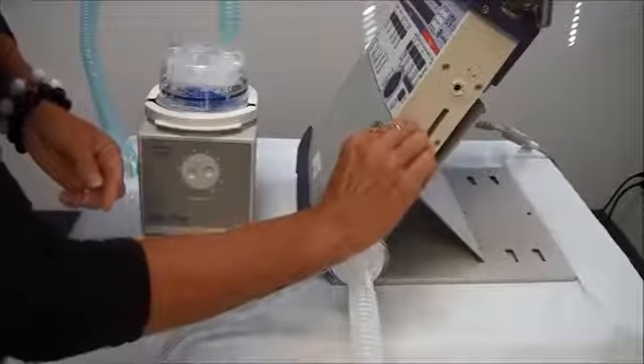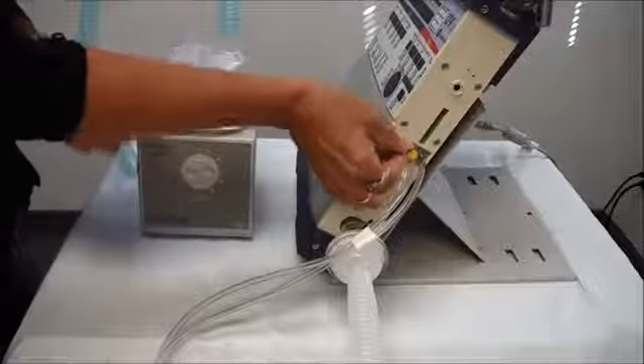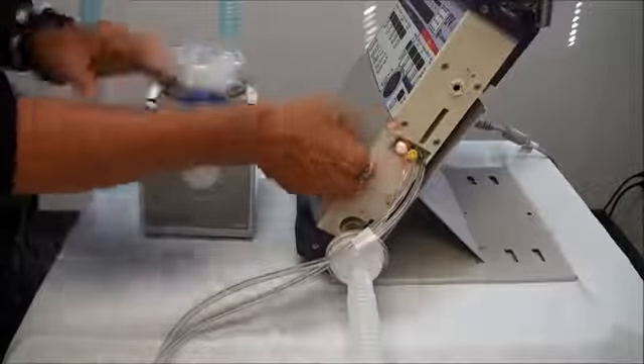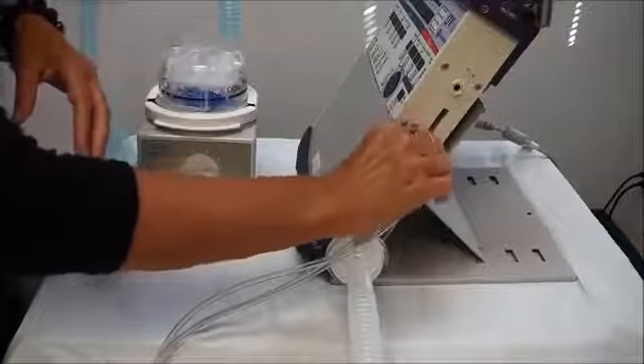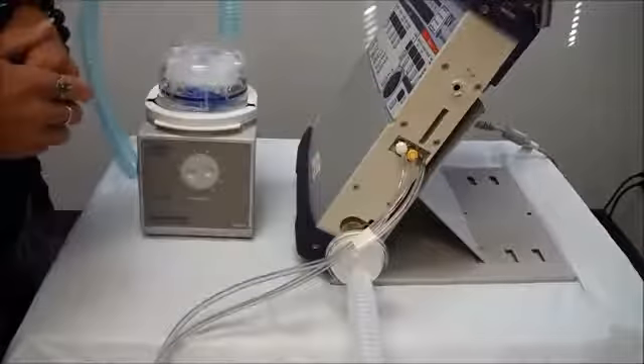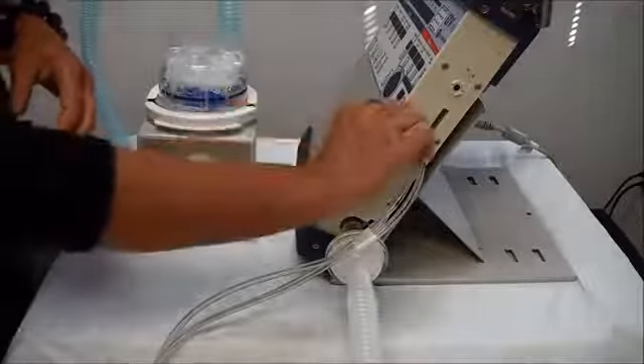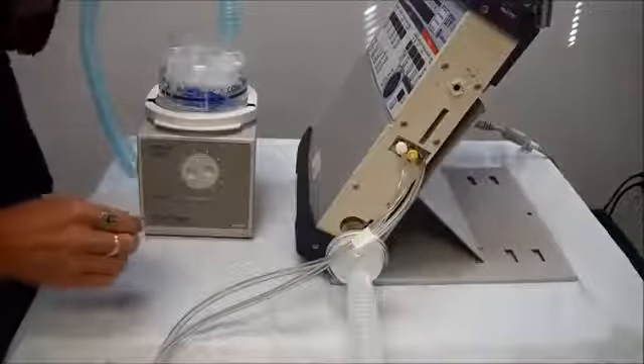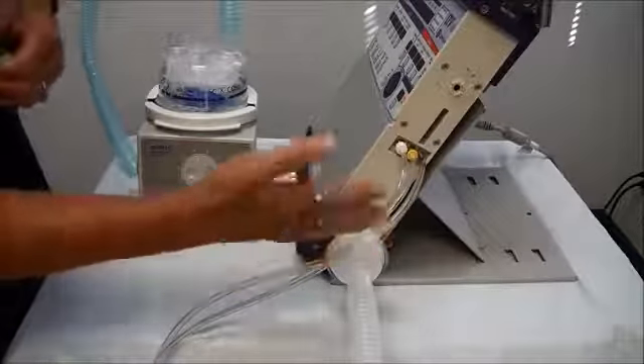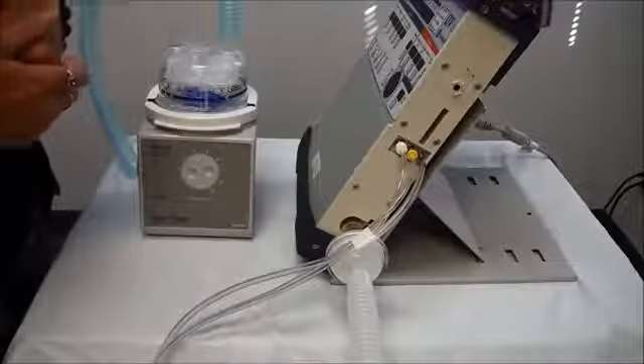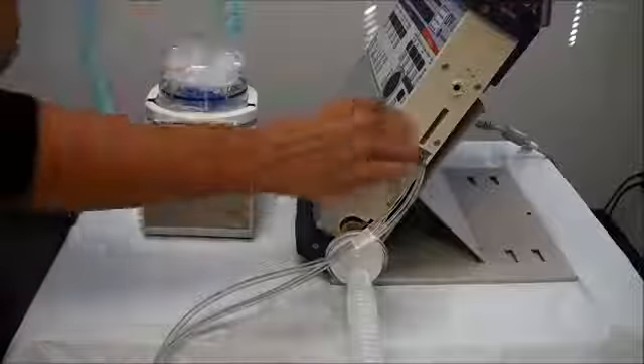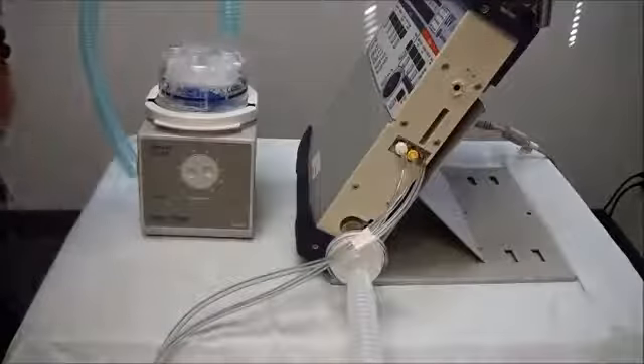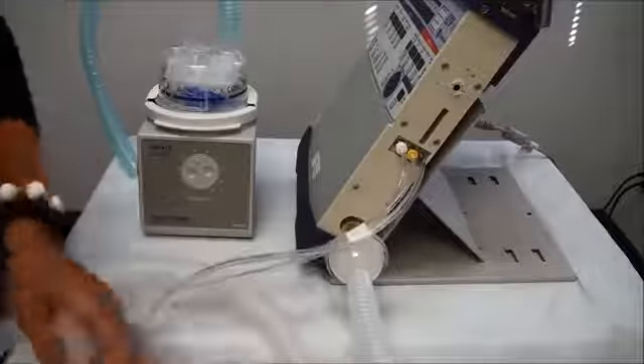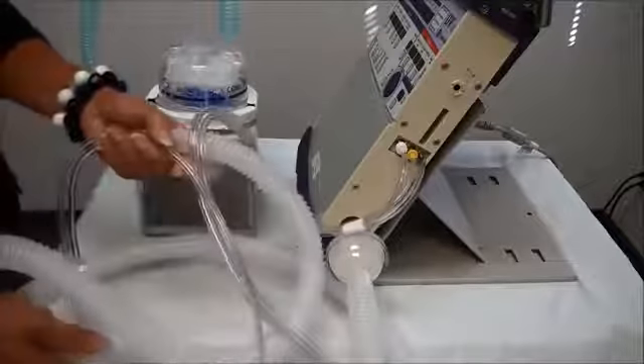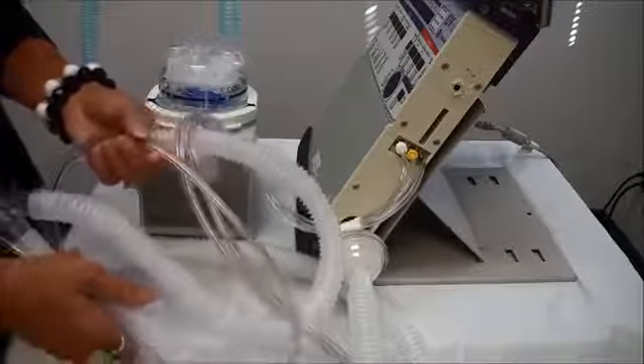If you don't get these on correctly or tight enough, you're going to get a disc sense alarm on your ventilator. So if you ever get that alarm, that's something you can check, is to make sure that your sensing lines are attached correctly, and also that you haven't gotten any condensation in that tubing. So this is what it's going to look like when it's connected correctly. And your tubing circuit then, this is just a tubing circuit that you would use without a humidifier.